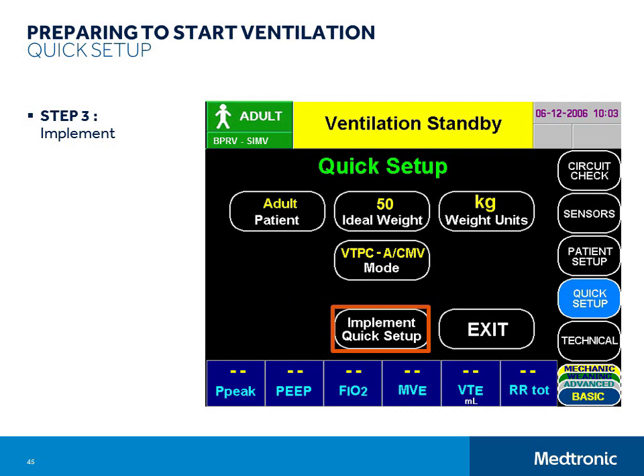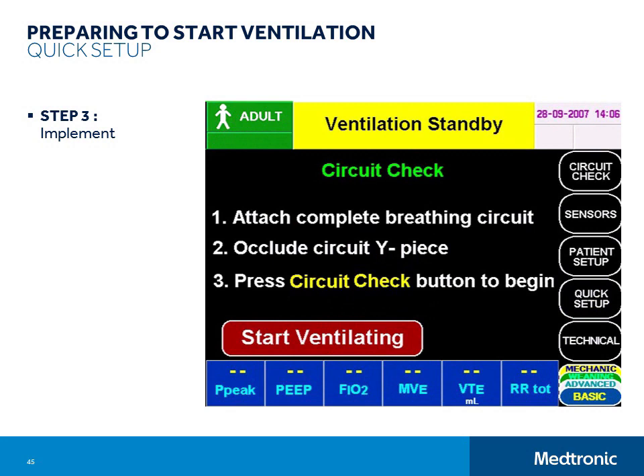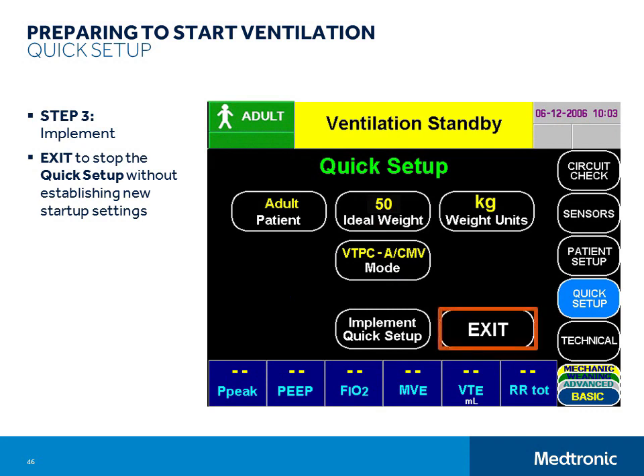If you touch the Exit button instead of the Implement Quick Setup, you will stop the quick setup without establishing new ventilator settings. You should check and, if necessary, readjust any ventilation or alarm settings that do not meet your clinical goals for the patient before connecting the ventilator to the patient.